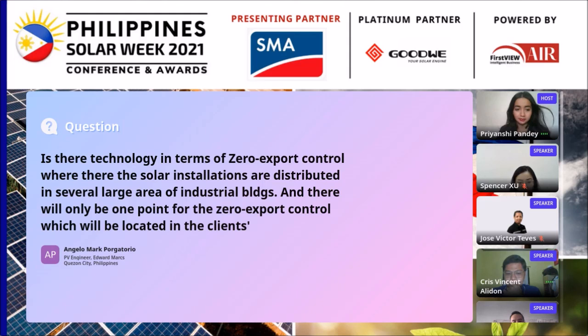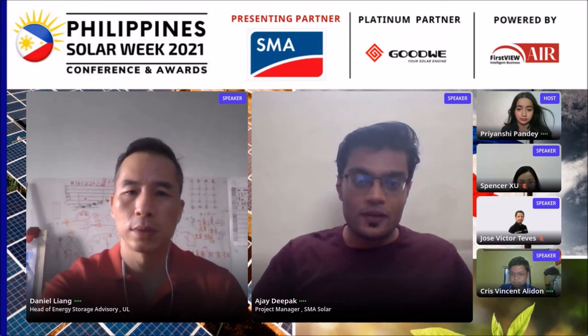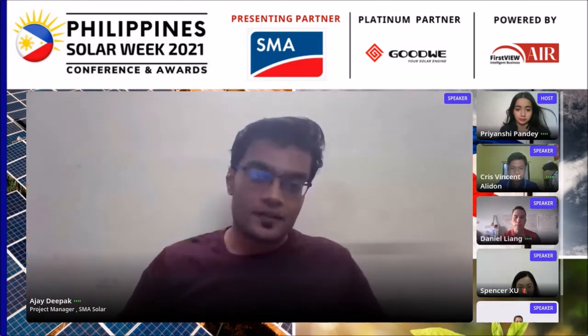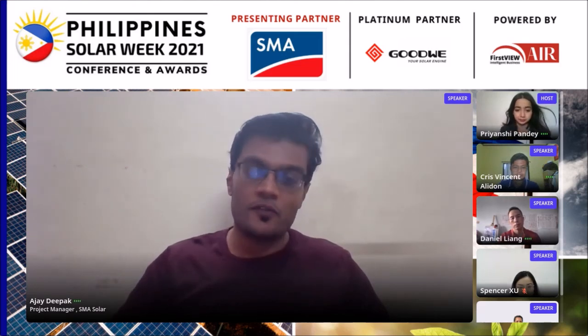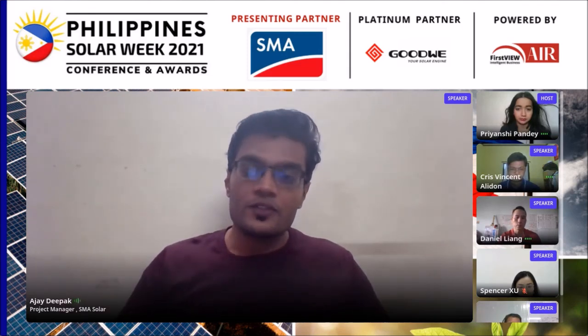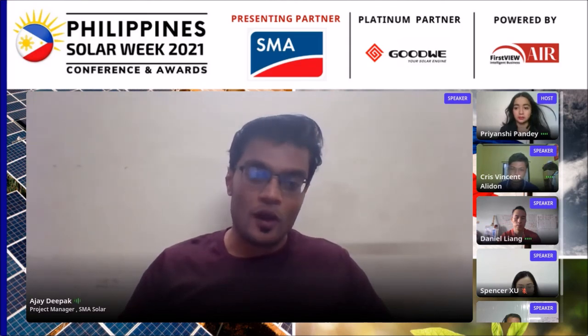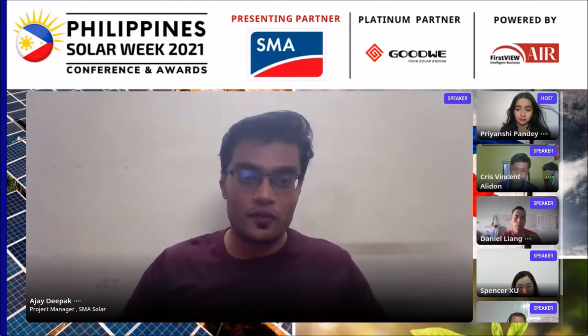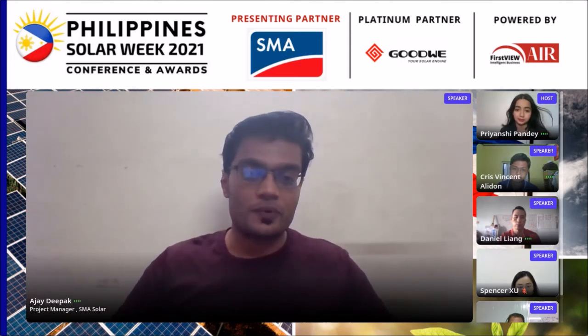In terms of zero export control when solar installation involves multiple buildings, this is technically possible only when you have a single common meter. Let's say you have a big factory with 10 different buildings and 1 megawatt installed on each, totaling 10 megawatts, and you want zero export. This is only possible if there is one common meter feeding power to the grid. Without a common meter, zero export isn't possible for the entire 10 megawatts — only for whatever capacity feeds into that single meter.